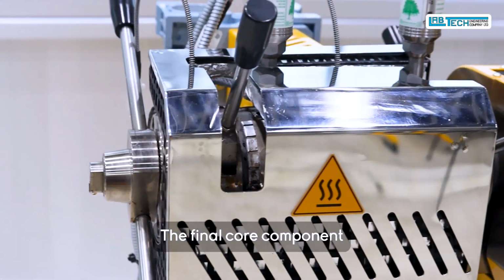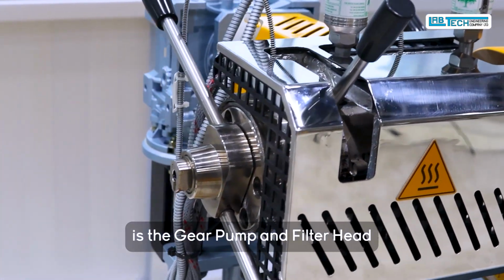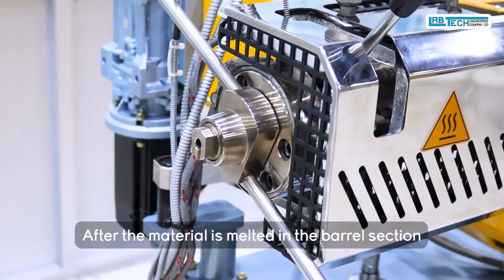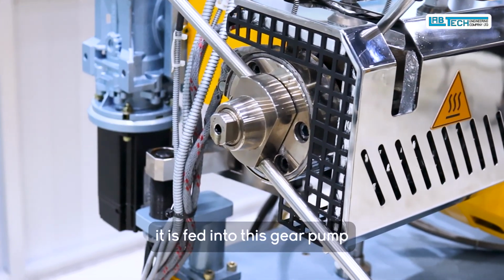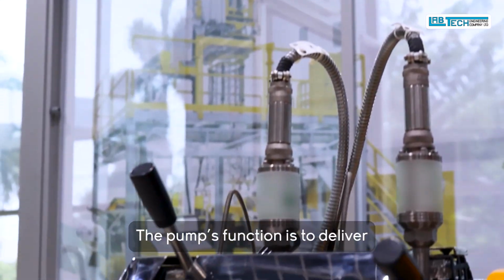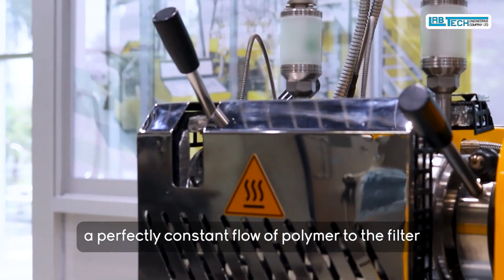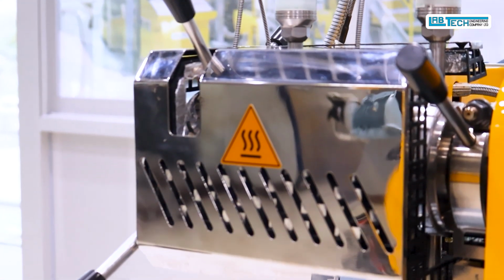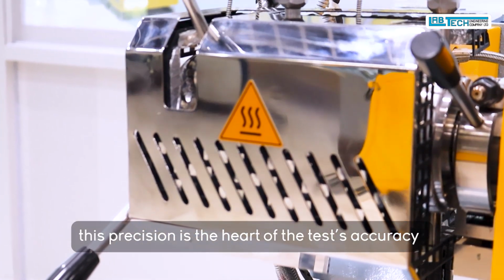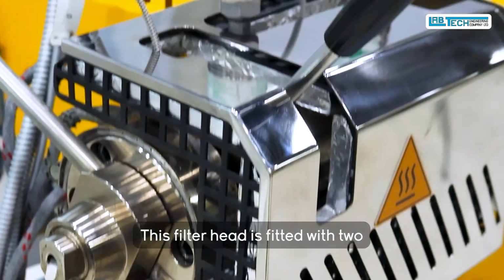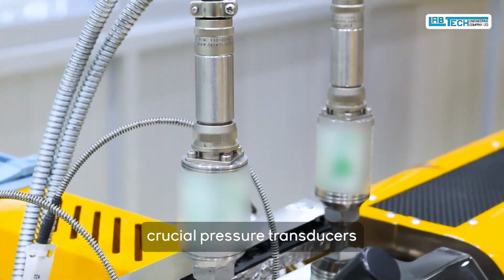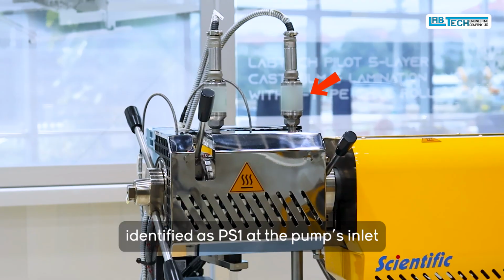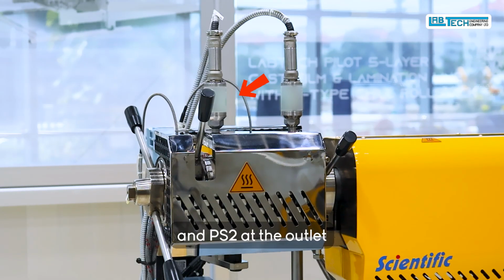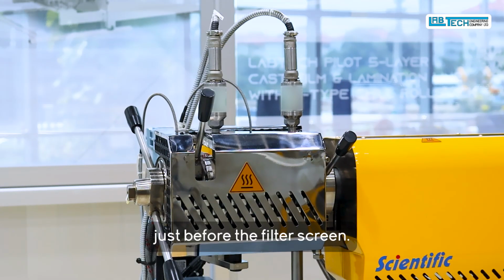The final core component is the gear pump and filter head. After the material is melted in the barrel section, it is fed into this gear pump. The pump's function is to deliver a perfectly constant flow of polymer to the filter. This precision is the heart of the test's accuracy. This filter head is fitted with two crucial pressure transducers, identified as PS1 at the pump's inlet and PS2 at the outlet, just before the filter screen.